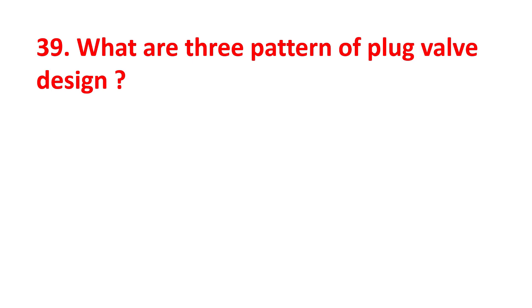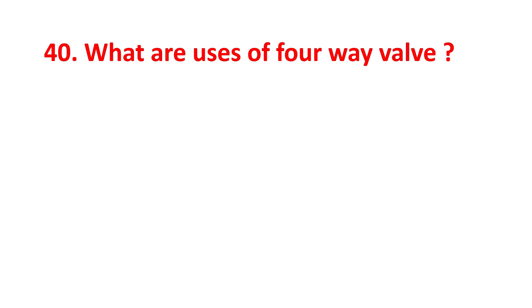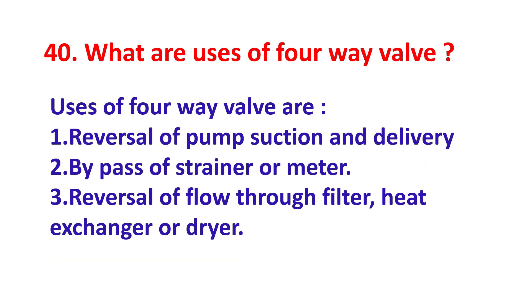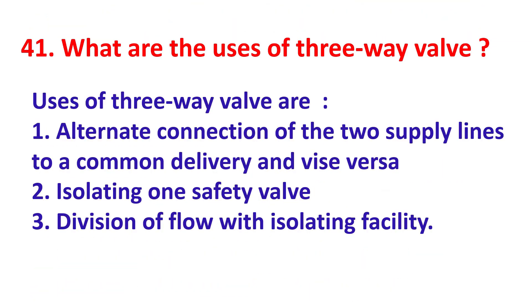What are the three patterns of plug valve design? They are regular pattern, short pattern, and venturi pattern. What are the uses of a four-way valve? Uses include reversal of pump suction and delivery, bypass of a strainer or meter, and reversal of flow through a filter, heat exchanger, or dryer. What are the uses of a three-way valve? Uses of a three-way valve are interconnection of two supply lines to a common delivery and vice versa, isolating one safety valve, and division of flow with isolating facility.